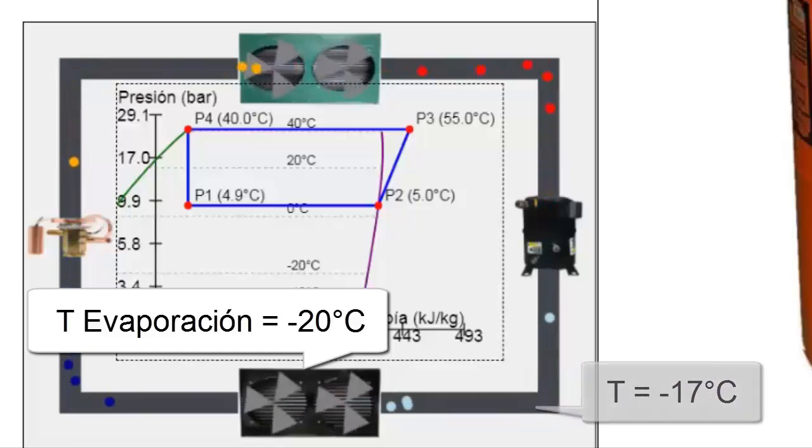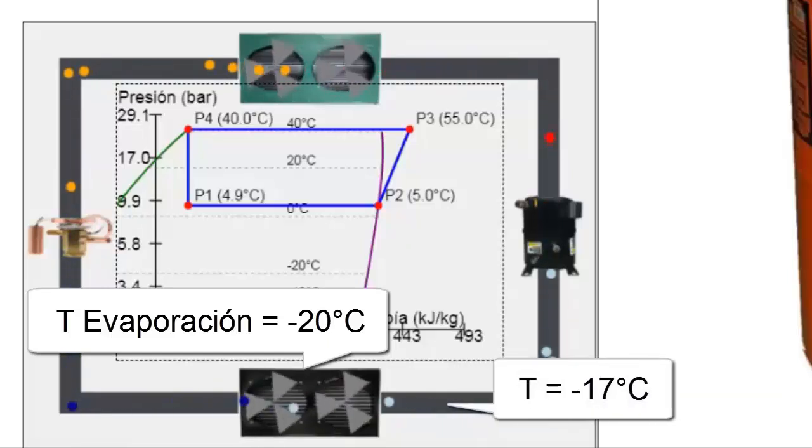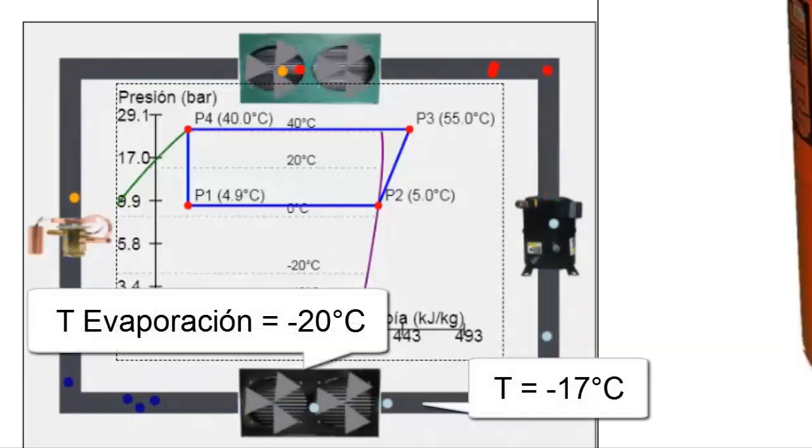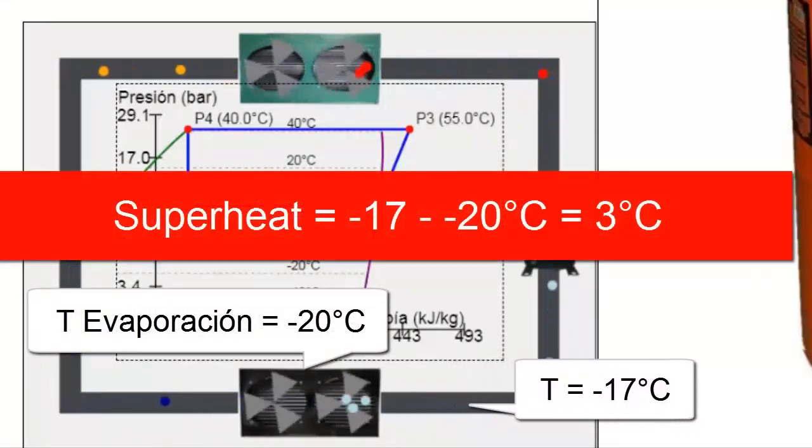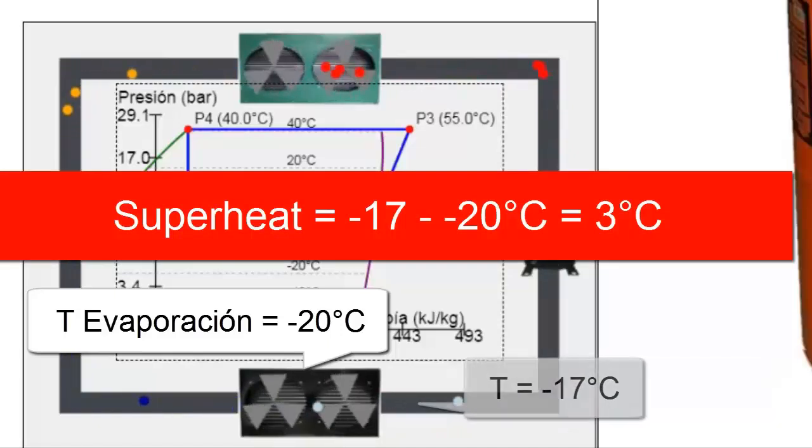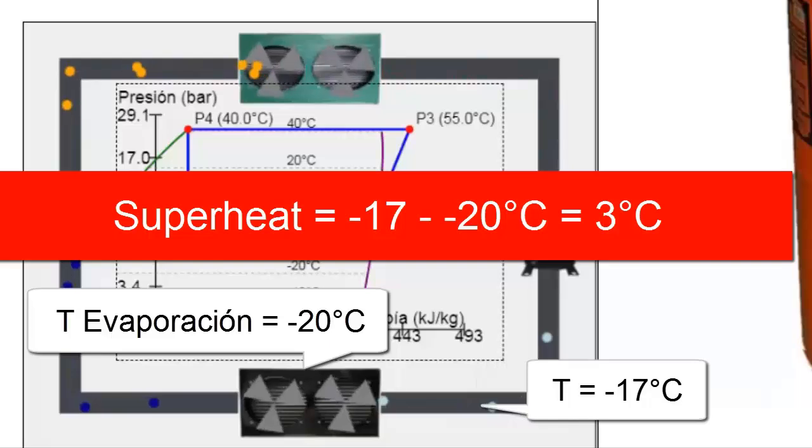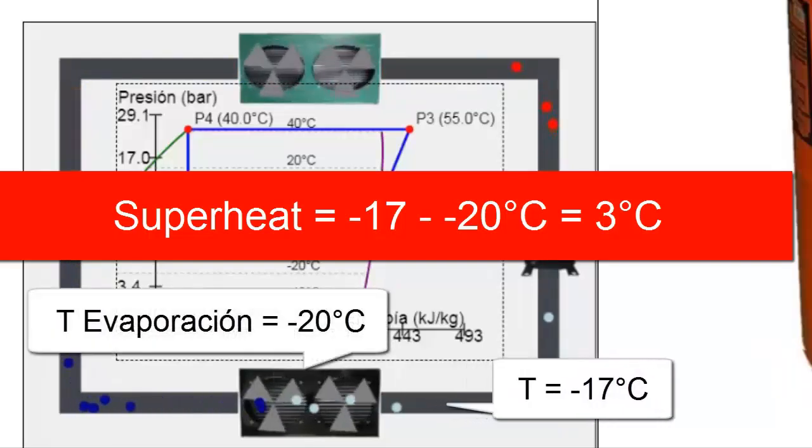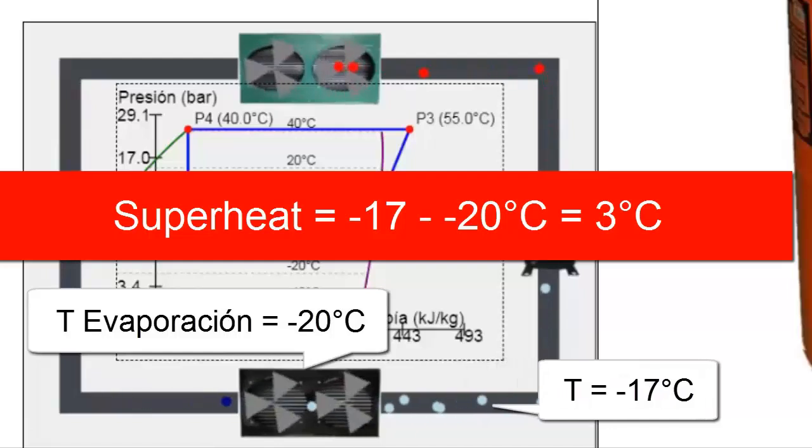The superheat value varies depending on the thermal load of the system. For example, in a freezer with a large quantity of food, the superheat can exceed 3 degrees Celsius, whereas with a lower thermal load, the superheat will be below 3 degrees Celsius, even reaching 0 degrees Celsius when the cooling load is very low.